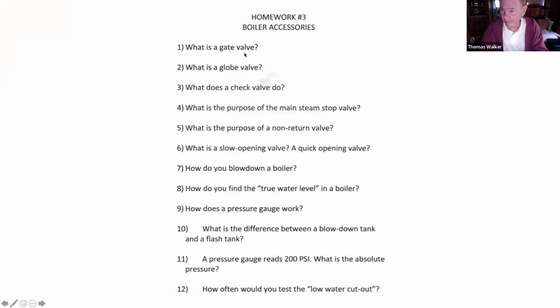Did we talk about gate valves, globe valves, check valves, main steam stop valves, the purpose of a non-return valve? Anybody remember the difference between a slow opening valve and a quick opening valve? Number of turns. The number of turns it takes to get it fully open, right? Greater than 5 full turns, it's a slow opening valve. Less than 5 full turns, quick opening valve. Most quick opening valves open in a quarter turn.